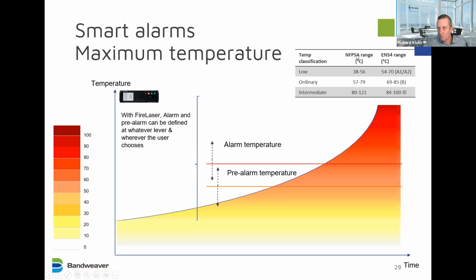What we find is with NFPA and EN 54, they have different categories. And so depending on how you configure the system, you may do it differently for different categories. We see quite often in standard environments, 58 degrees C is roughly where the alarm temperature is set, but you do vary according to conditions. And the important note is that it's defined in the software, not the hardware.